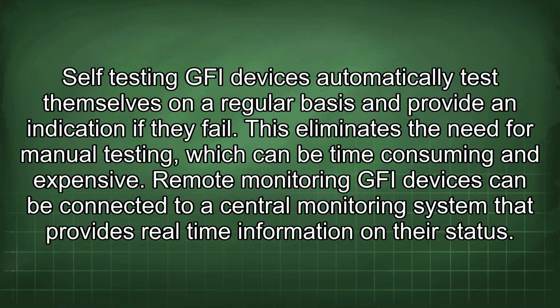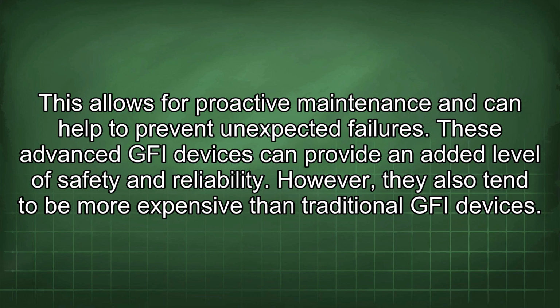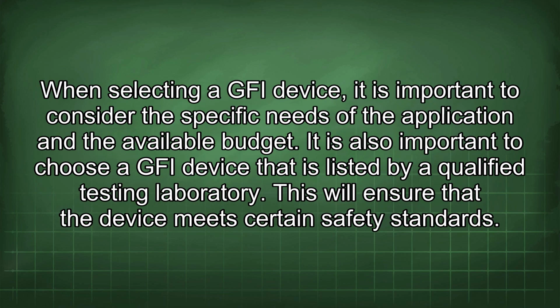Remote monitoring GFI devices can be connected to a central monitoring system that provides real-time information on their status. This allows for proactive maintenance and can help to prevent unexpected failures. These advanced GFI devices can provide an added level of safety and reliability. However, they also tend to be more expensive than traditional GFI devices. When selecting a GFI device, it is important to consider the specific needs of the application and the available budget.